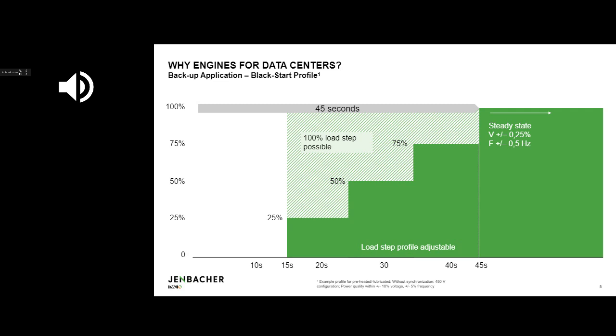You can see in this example we have G4 performance because on load application, the frequency and voltage drop of a G3 class is 15%. Here we are achieving values of voltage drop of 10% and frequency drop of 5%. So this unit has much more transient response capability than a standard ISO level - top of the class performance, even starting fast and giving the power quality that the data center needs.